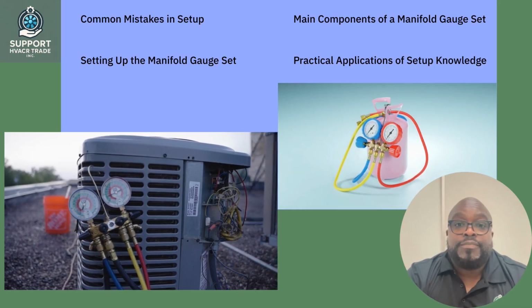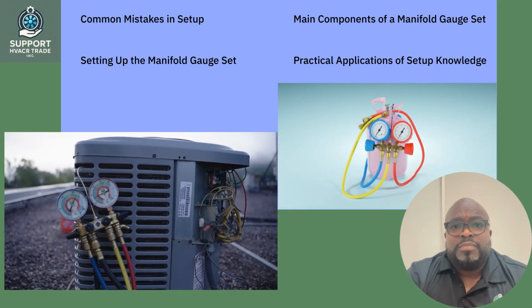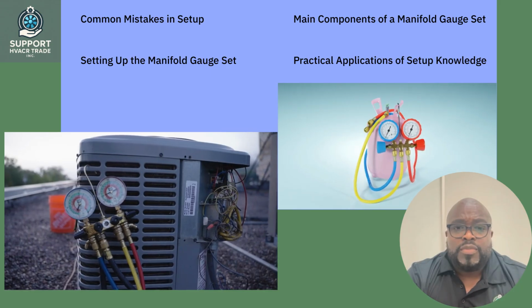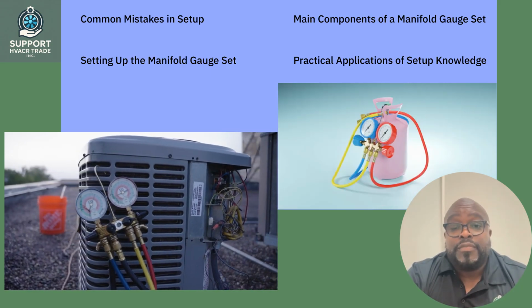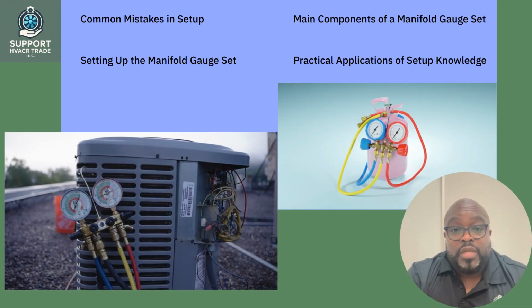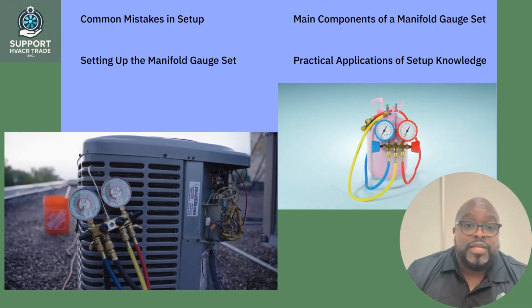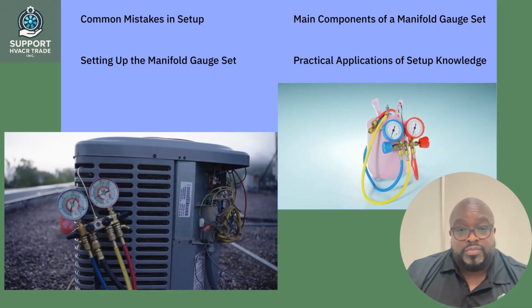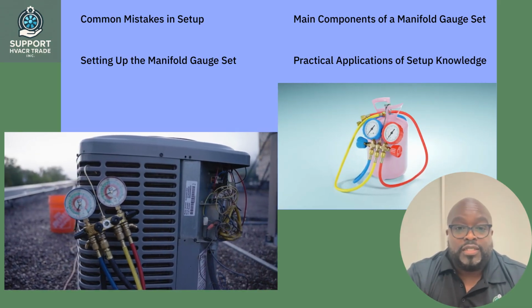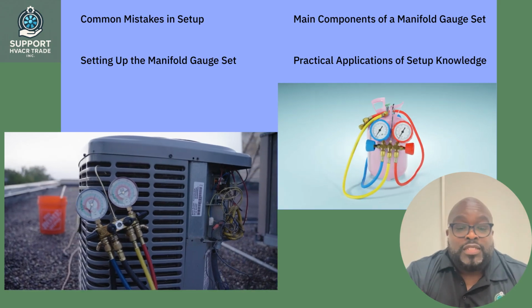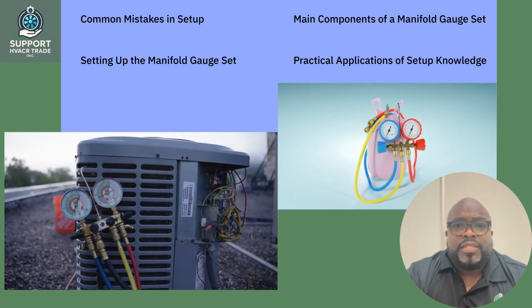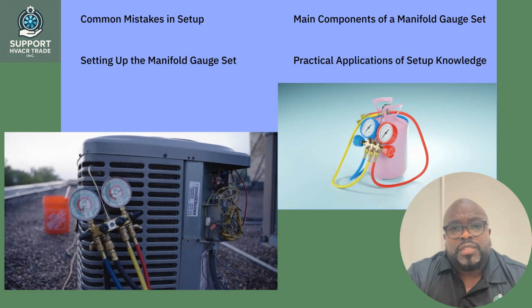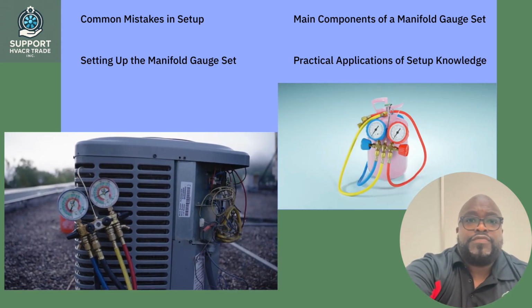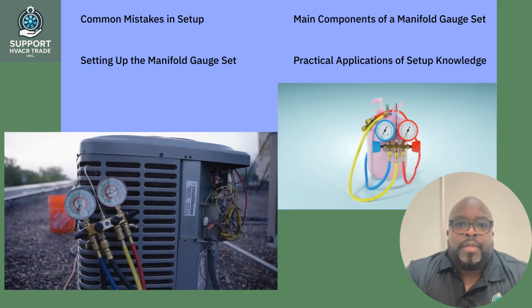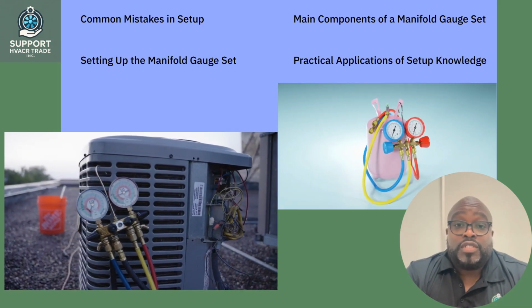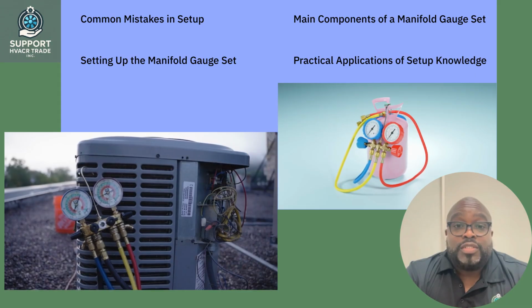Common mistakes in setup. Even seasoned professionals can make errors during setup. Here are some common mistakes to watch out for. Incorrect hose connections. Always ensure that the red hose is connected to the high pressure side and the blue hose to the low pressure side. Neglecting to check for leaks. Failing to inspect hoses and connections can lead to refrigerant leaks, which are both dangerous and can affect system performance. By being aware of these mistakes, you can avoid them and ensure a smooth setup process.